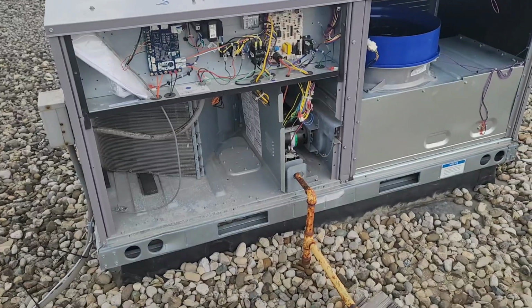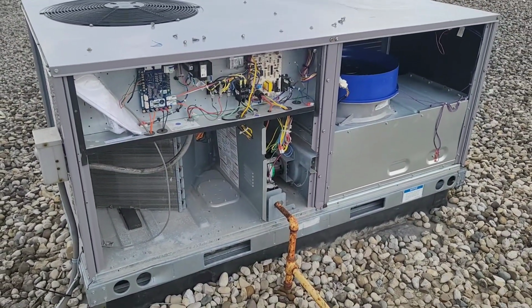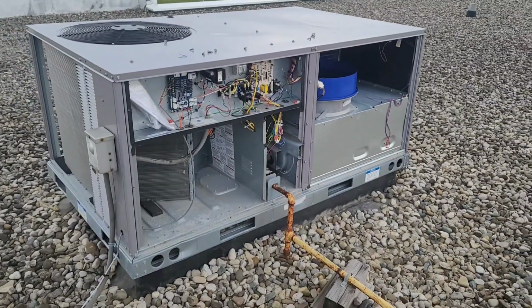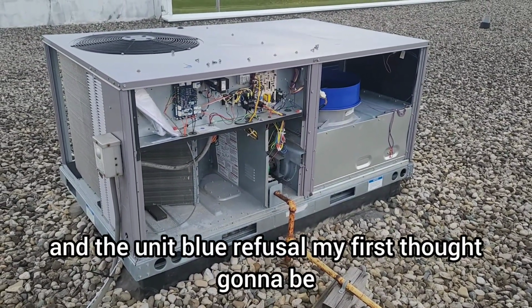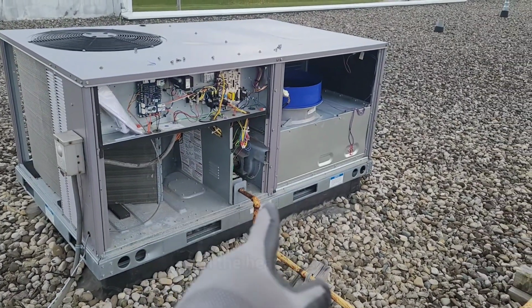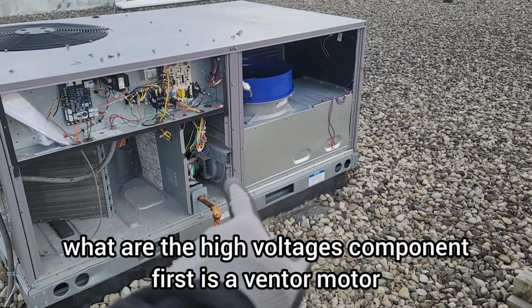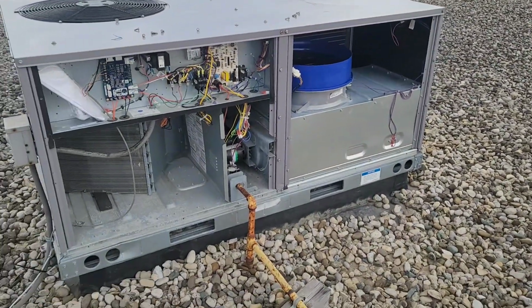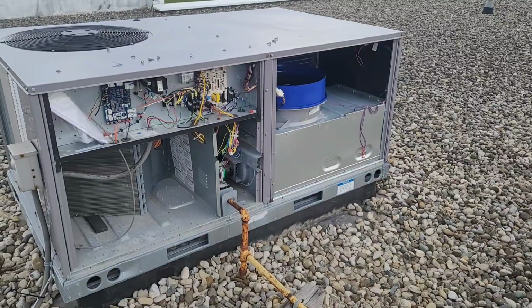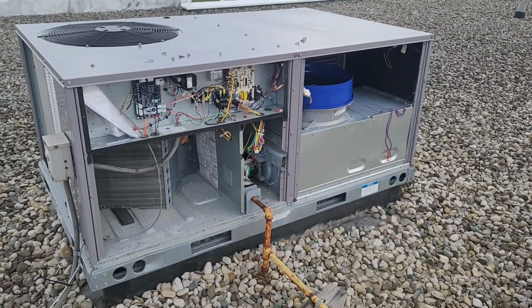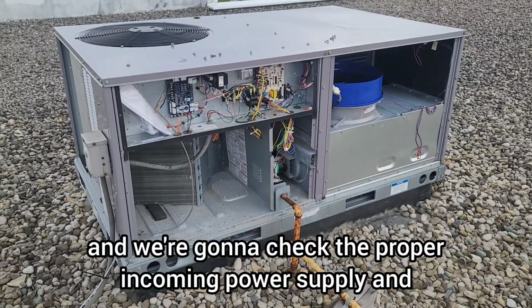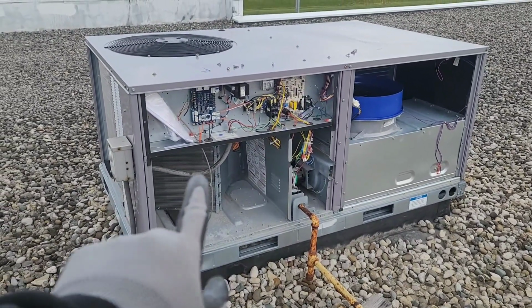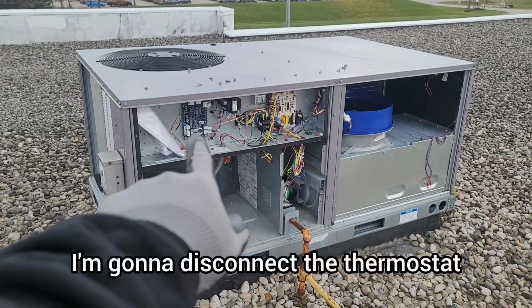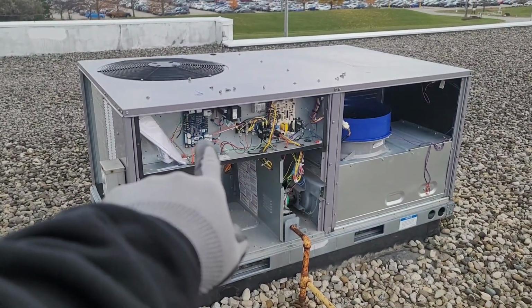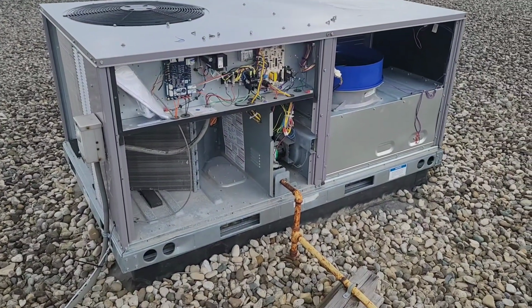So it's November and the ambient temperature is like 5-6, and definitely it's a cold season, and the unit blew fuses. My first thought is going to be on the heating side: what are the high voltage components? First is the venter motor and the second one is the blower motor. So we're gonna check those for short to ground, and we're gonna check the proper incoming power supply. And before turning on the power, I'm gonna disconnect the thermostat R terminal from the control board. Okay, let's start.